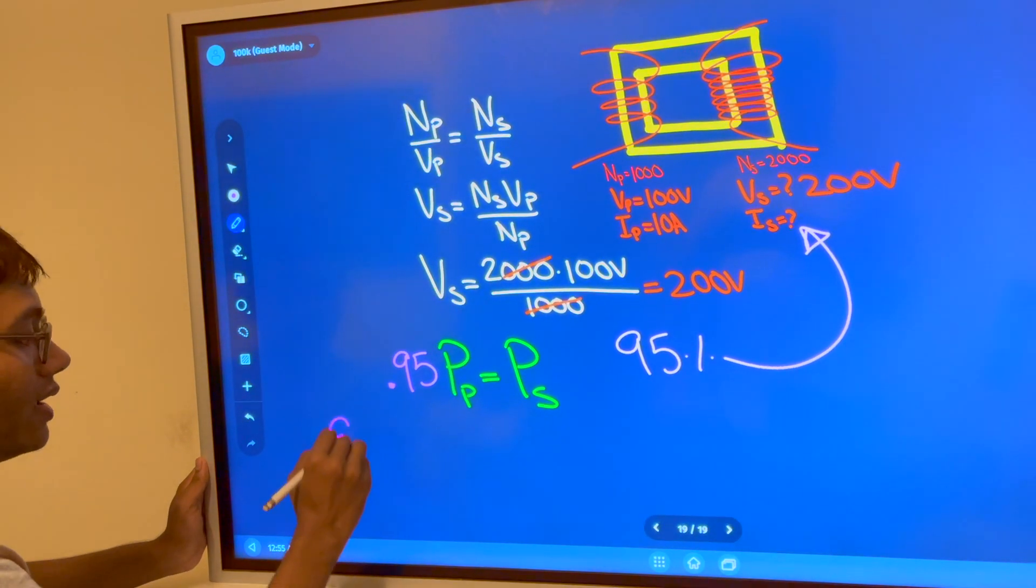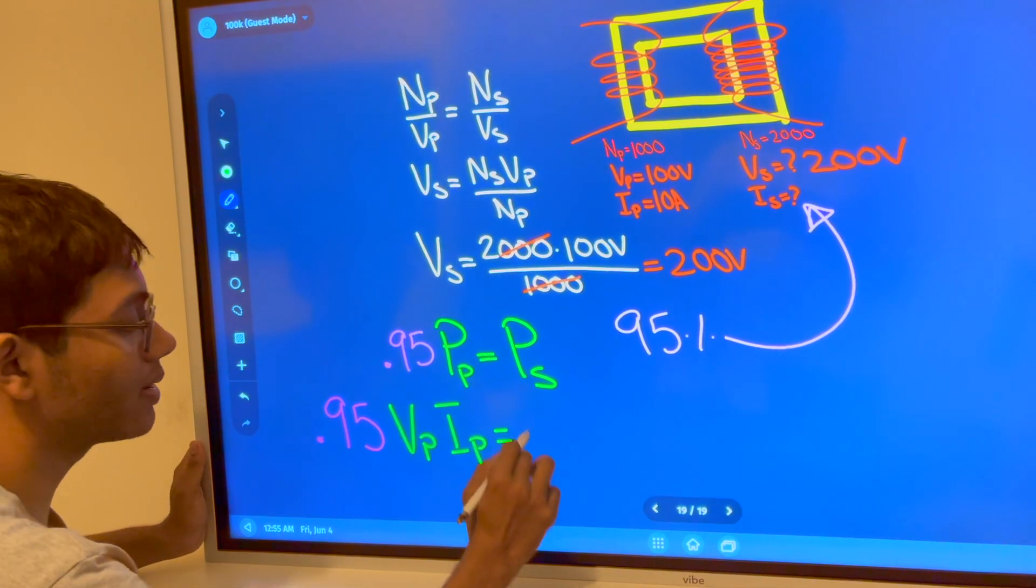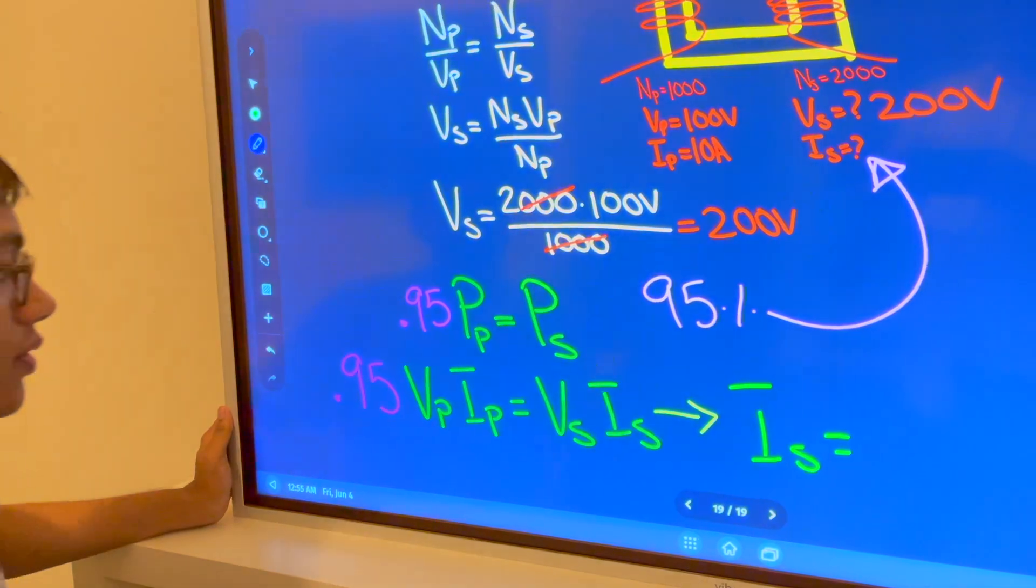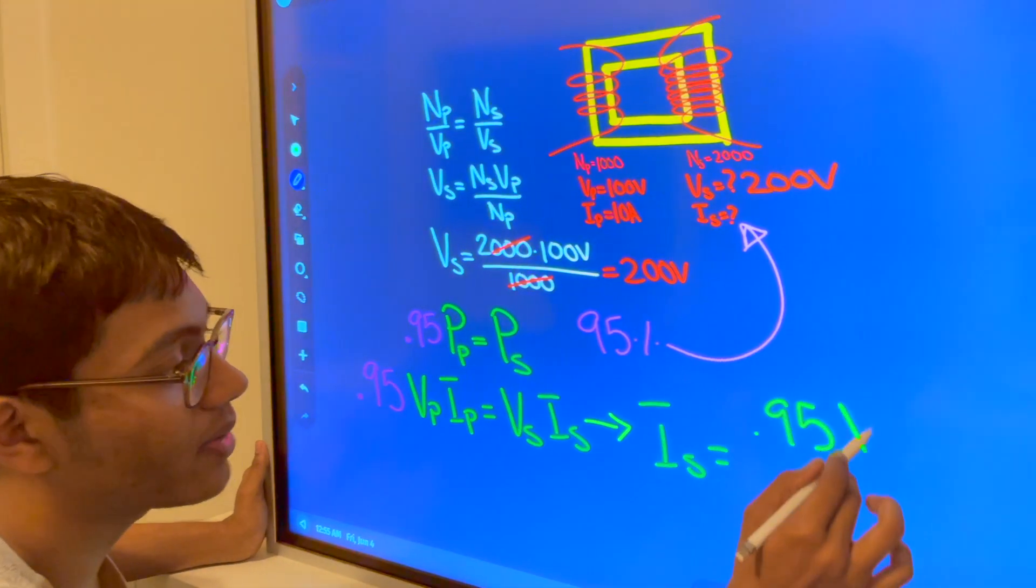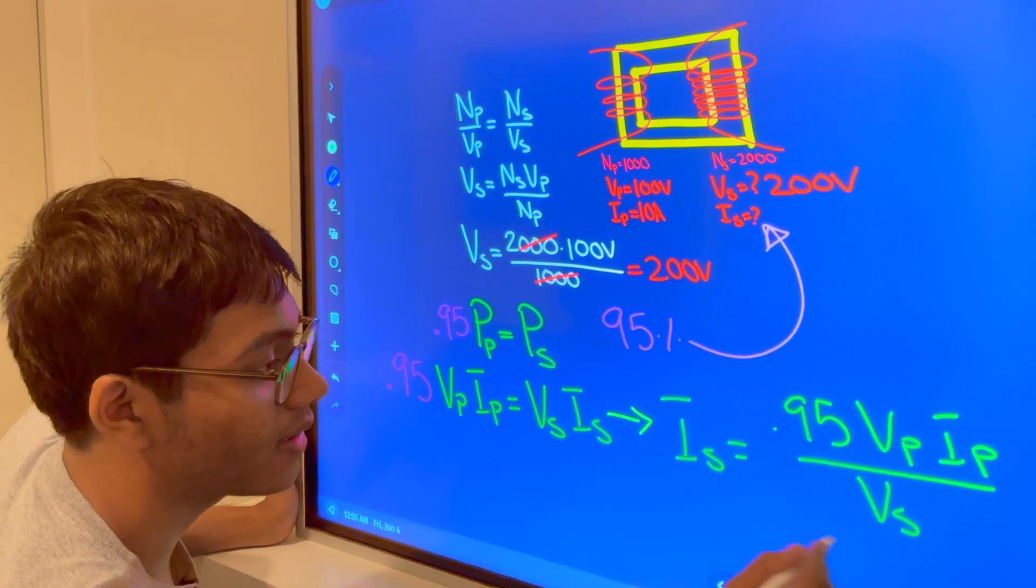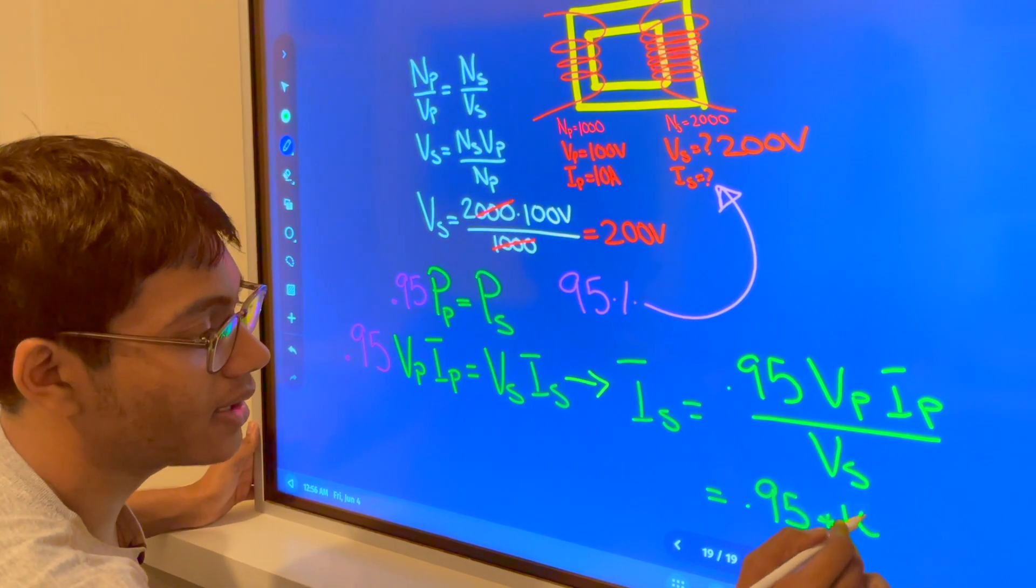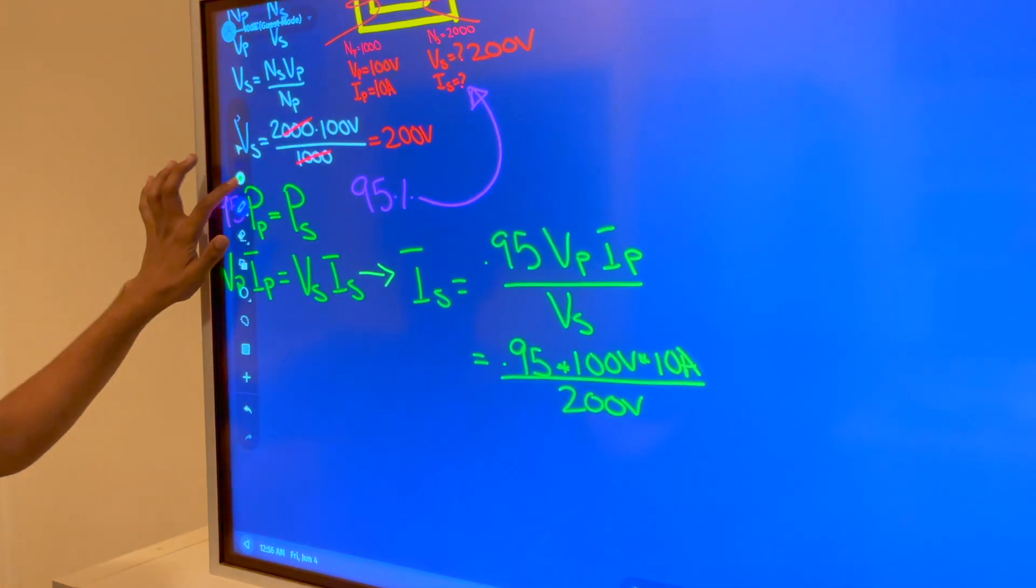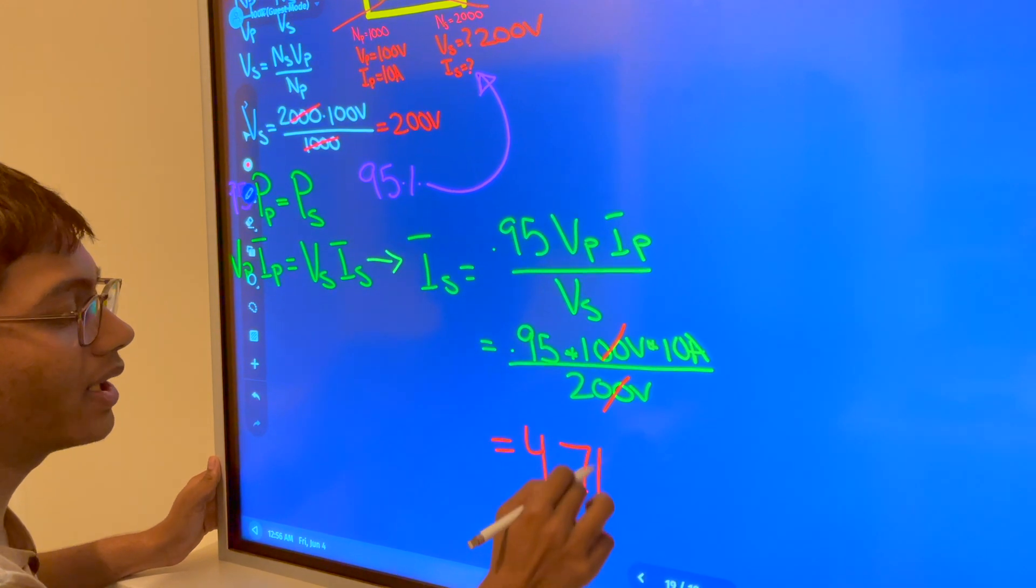What's the primary power? Power is voltage times current. So the primary voltage times the primary current equals the secondary voltage times the secondary current. If I plug in everything: Is = 0.95 × Vp × Ip / Vs. The primary voltage is 100 volts, the primary current is 10 amps, and the secondary voltage is 200 volts. If I simplify everything, my final answer is about 4.7 amps.